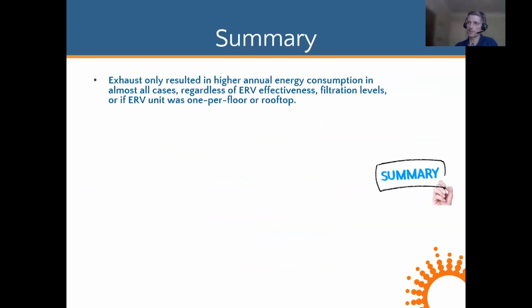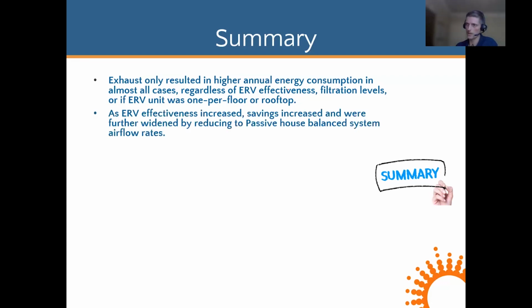All right, so quick summary. The exhaust-only scenario resulted in higher annual energy consumption in almost all cases, regardless of the ERV effectiveness, filtration levels, or if the ERV unit was one per floor or a rooftop unit. As effectiveness increased in the ERV, savings increased, and these were further widened by reducing the airflow levels.